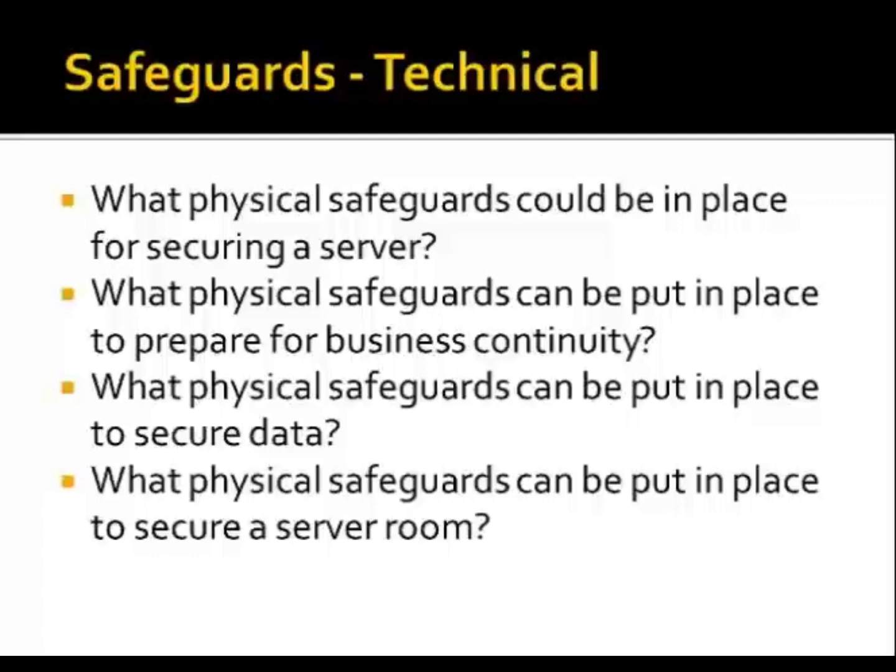The other one is I've had companies where they put all of their servers on backup power but not monitors, so they couldn't see what was going on. They couldn't administer the environment. They put all the servers on but no air conditioning, so they couldn't air condition the room, so they had to shut down all the servers anyway. Most backup power, and phone system, you need to have all the phones and the network, because they're all VoIP phones now, and the phone system on backup power as well. So if you put it all on backup power, you're only going to be able to run for a minimum amount of time. So the idea is it gives most companies what we would call a graceful shutdown, and they shut down business.